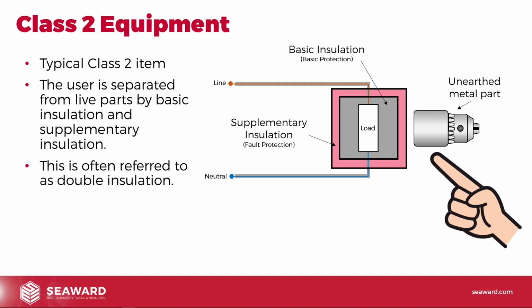Now, it is still possible to get metal cased class 2 equipment. So class 2 equipment may have metal parts. It may have a full metal case. You think of something like maybe a DVD player. It might have a metal box around it, but generally it's got a figure of 8 lead. It's a class 2 appliance, and there's 2 layers of insulation in there, the double insulation inside the appliance. If we put a metal box around the outside of that, it doesn't matter. It doesn't need to be earthed because it's not going to become live under fault conditions.